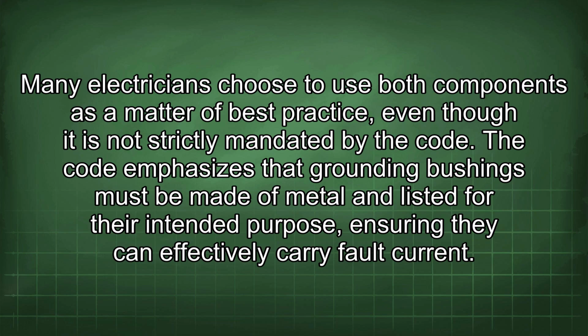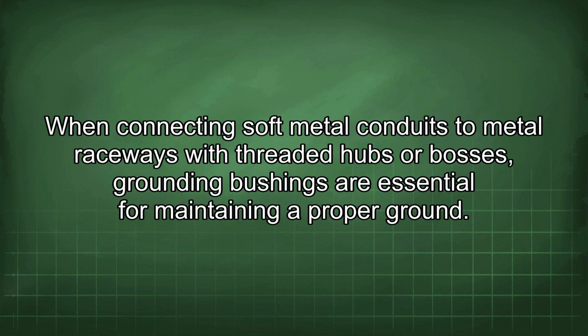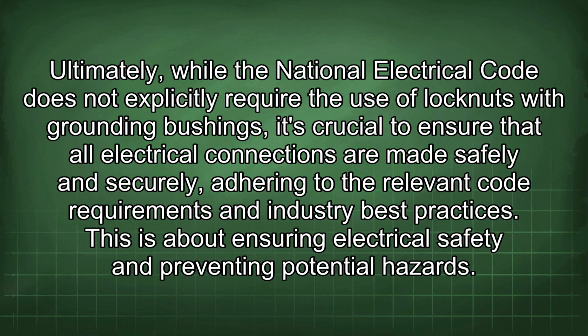The code emphasizes that grounding bushings must be made of metal and listed for their intended purpose, ensuring they can effectively carry fault current. When connecting soft metal conduits to metal raceways with threaded hubs or bosses, grounding bushings are essential for maintaining a proper ground. Ultimately, while the National Electrical Code does not explicitly require the use of locknuts with grounding bushings, it's crucial to ensure that all electrical connections are made safely and securely, adhering to the relevant code requirements and industry best practices. This is about ensuring electrical safety and preventing potential hazards.